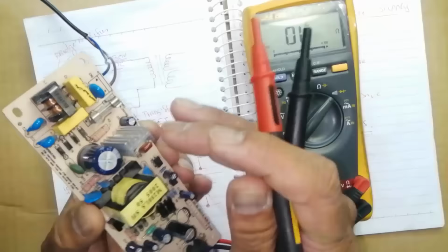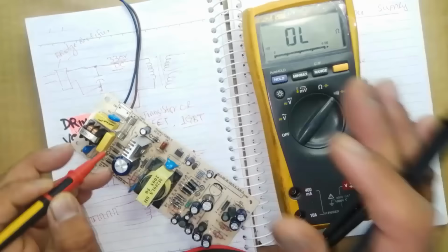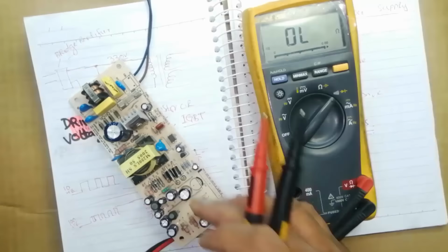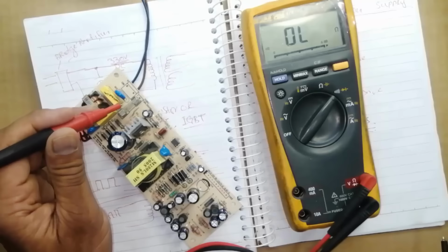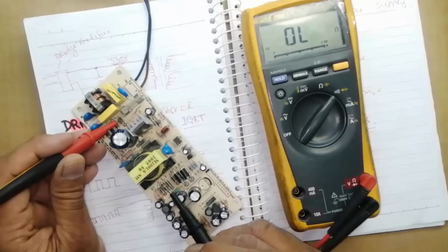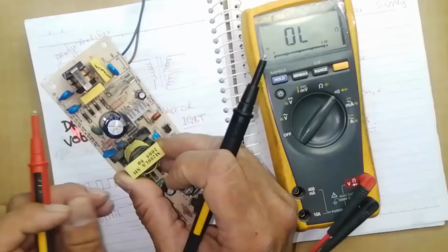Maybe the fuse is not good. If the fuse is giving continuity, that means it's okay. Okay, after that, the main issues. If the MOV is okay, thermistor is okay, and the fuse is burnt out, before replacing this fuse, go to these four diodes or go to this capacitor. Most of the time, this capacitor is short circuit internally. Remove this one and test it.